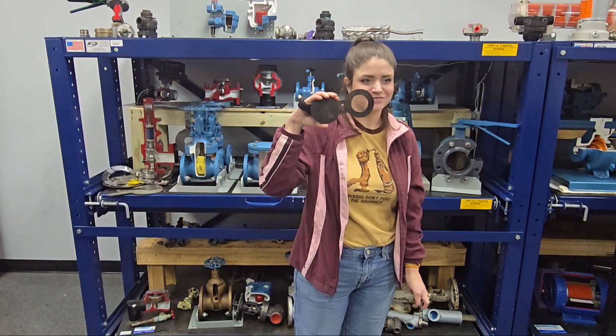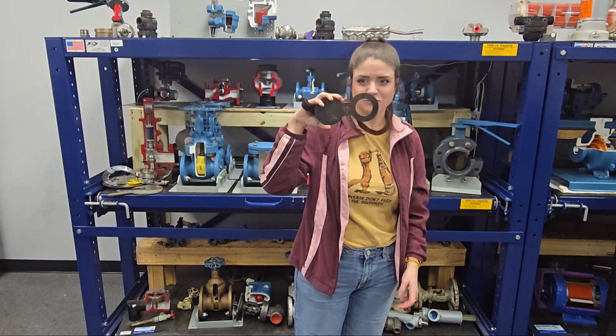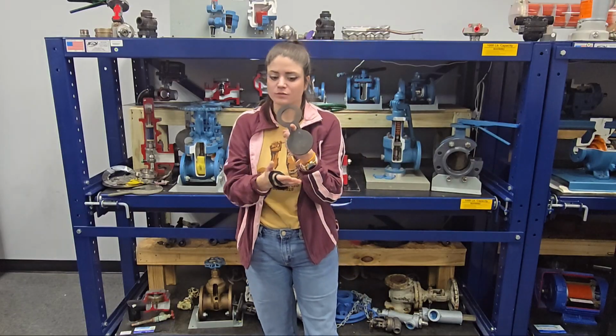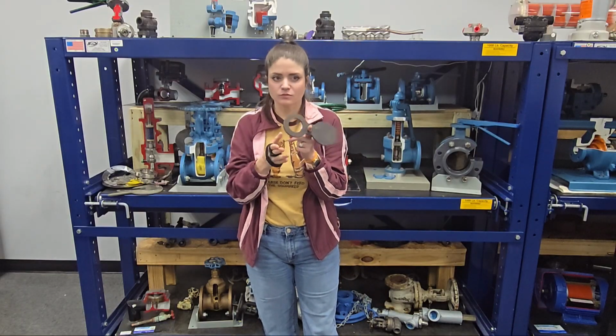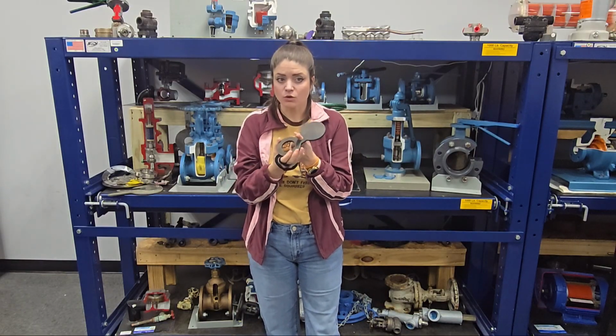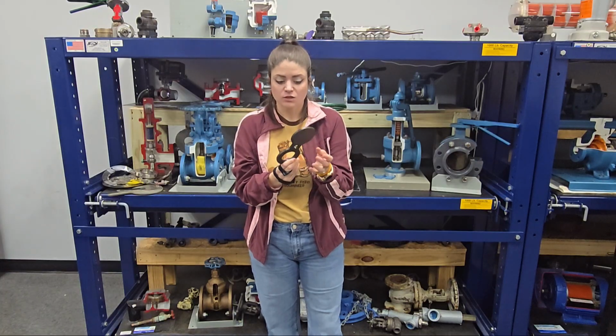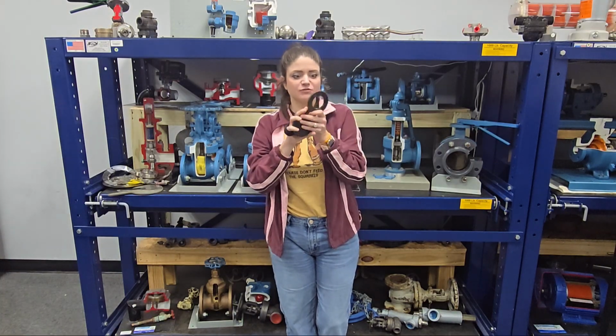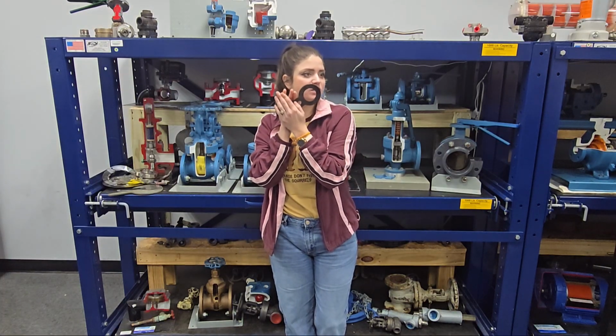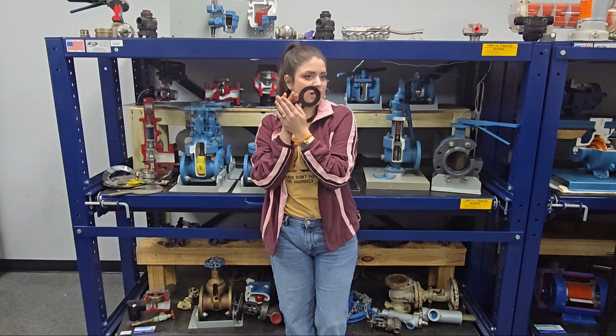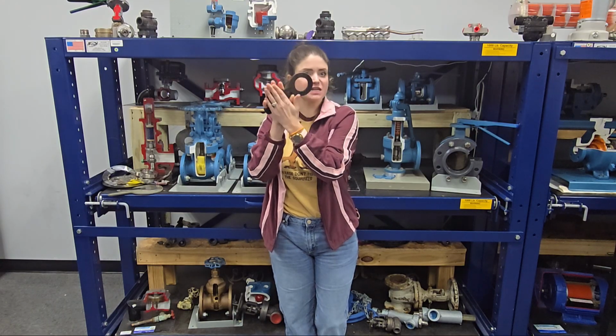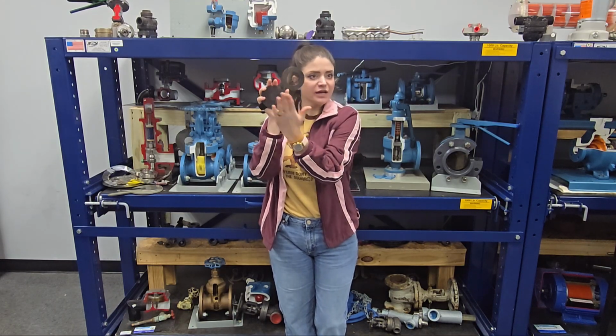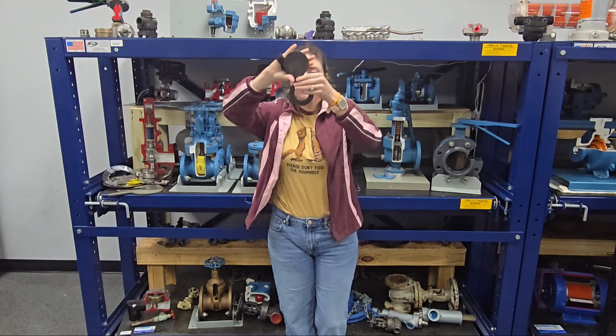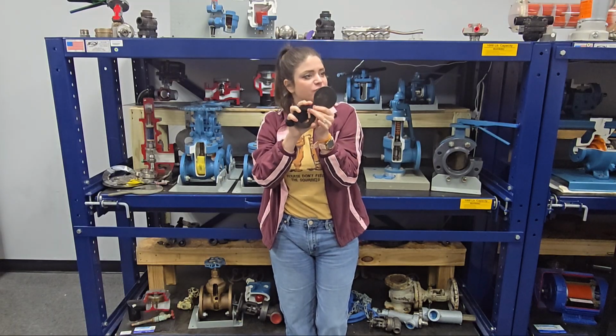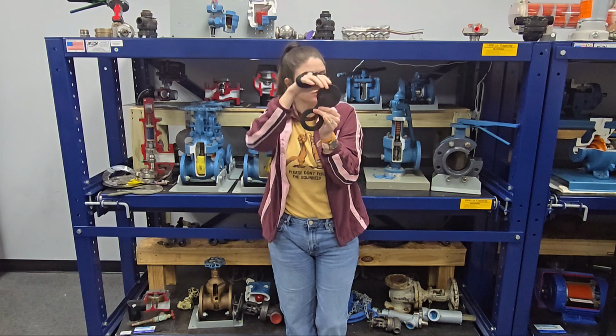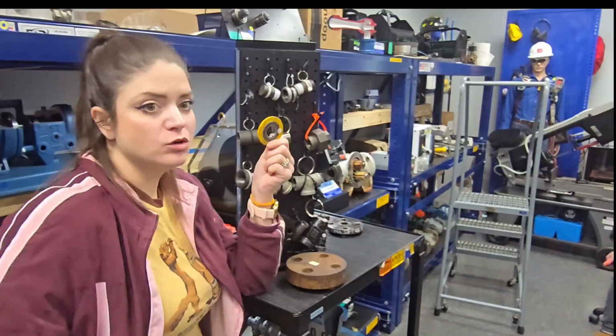Orifice plate. No, that's a blind flange, but you just keep it in there. Spectacle, or figure eight. So this stays in. If you see this part sticking out of the pipe, you know what's in. Paddle - if this is inside the pipe, this will be hanging out. You have your paddle blind in; when this side's in, it's just a spacer. That way, if you need to do an isolation, you can flip it.